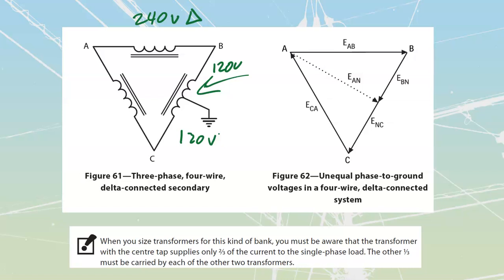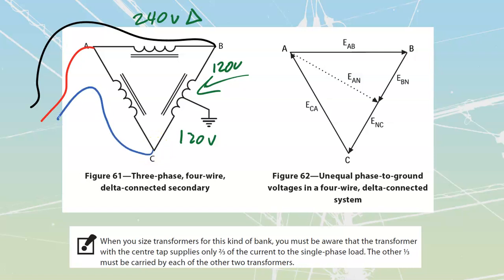What we'll do is take these systems, and then we're going to feed these lines. Over here we've got our A line. And what we're going to do is create 2 separate panels with these. So coming off this transformer's connection, you're going to have your B line, and you're going to have your C line. And these are going to go into a 3-phase panel that has no neutral. Has to go into a 3-phase, no neutral. Okay, those 2 are going to get fed into there, and then out of that one, we're going to distribute out to our different loads that we're going to have on the place.